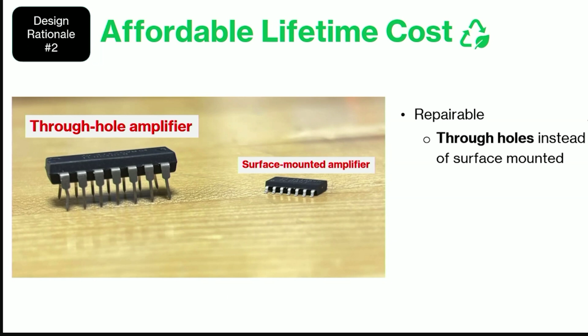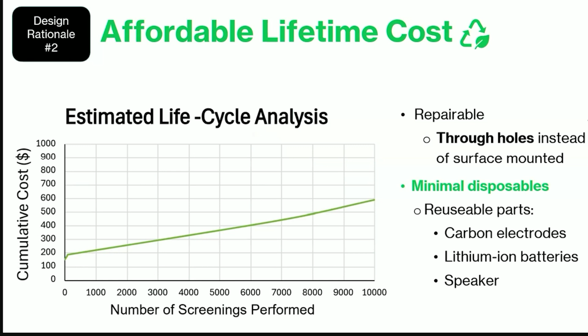Secondly, our design ensures affordable lifetime cost. We prioritized repairability by using through-hole components that are easier to replace and less susceptible to physical damage in low-resource settings. To minimize disposables, we implemented a system that uses a reusable speaker, electrodes, and batteries. Our life cycle analysis suggests that even after 10,000 newborn screenings are performed, the total lifetime cost will not exceed $600.